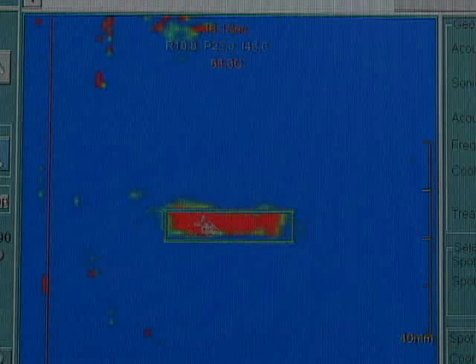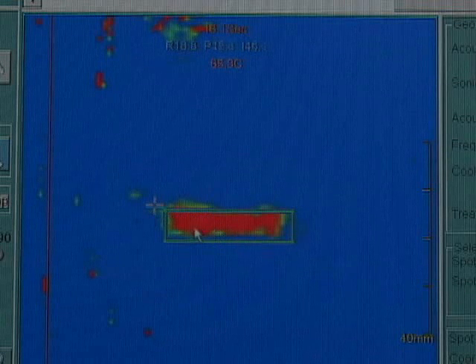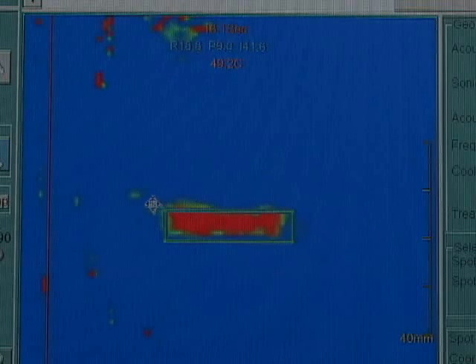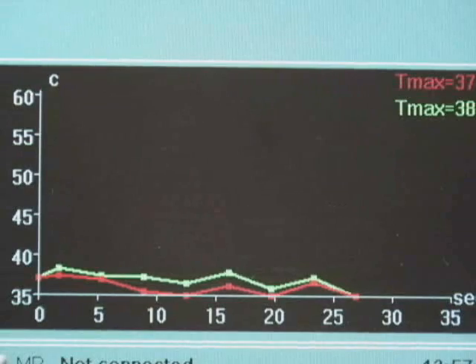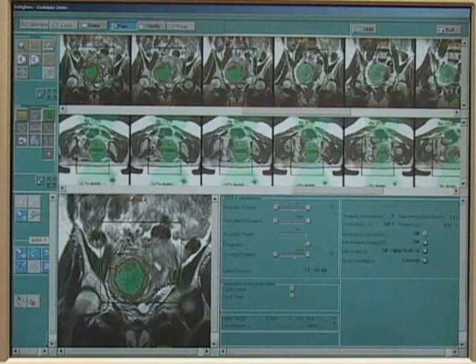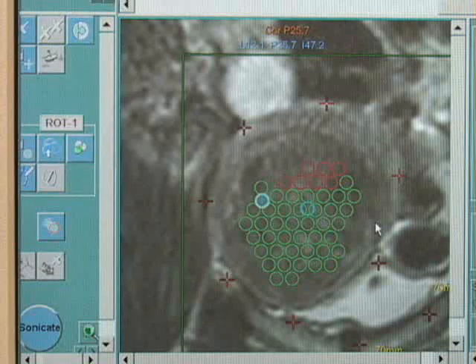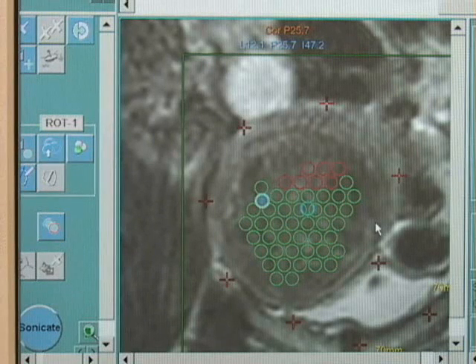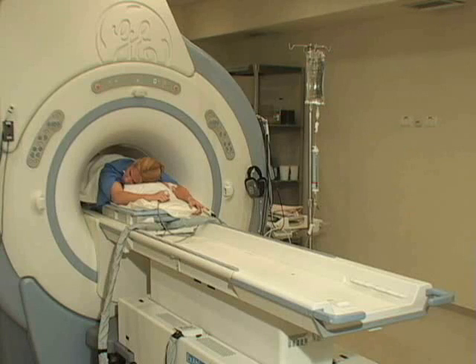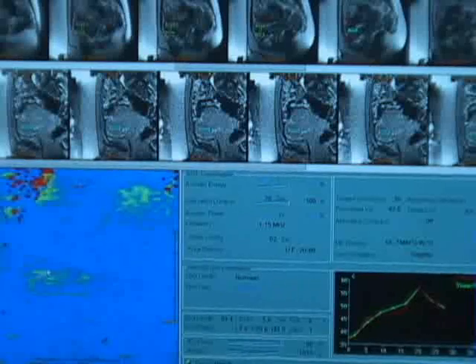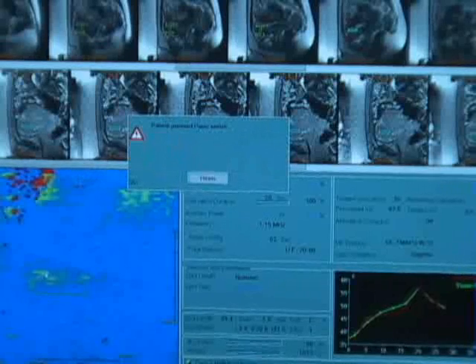The tissue temperature in the focal volume reaches 65 degrees, but because the temperature fall-off is sharp, the temperature of surrounding tissue is not raised. 4 millimeters from the spot, the temperature is normal body temperature. To increase treatment speed and safety, the system automatically develops a treatment map to maximize the number of successive sonications without beam path overlap. The patient receives only limited conscious sedation and provides feedback throughout the procedure. At any point, she can press the handheld Stop Sonication button to immediately stop the sonication in case of pain or discomfort.